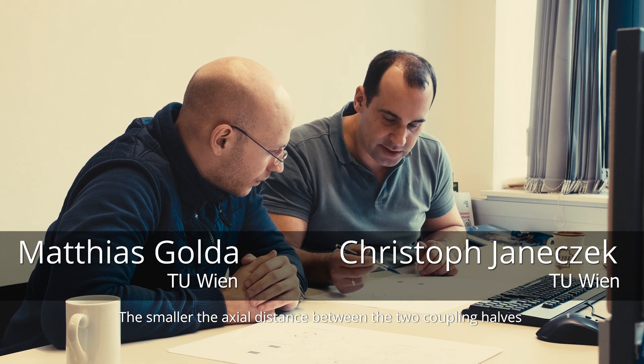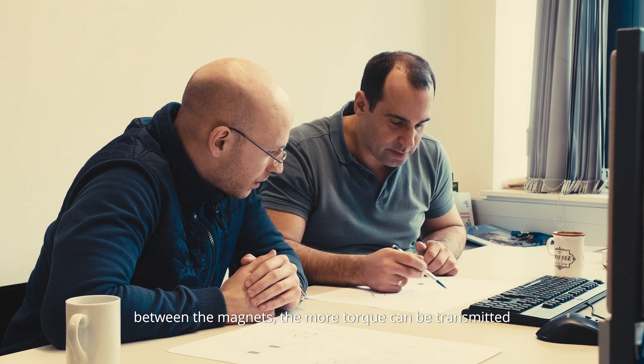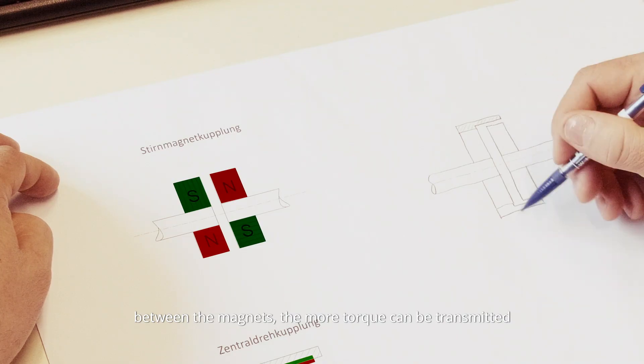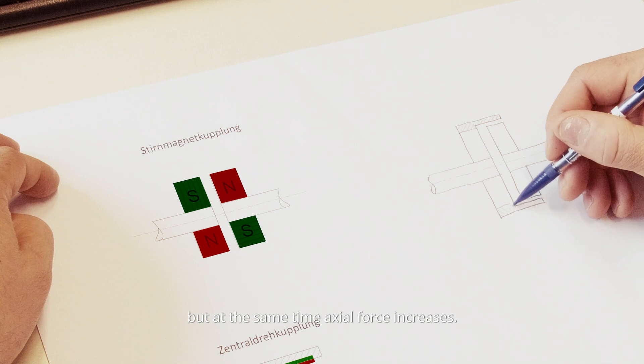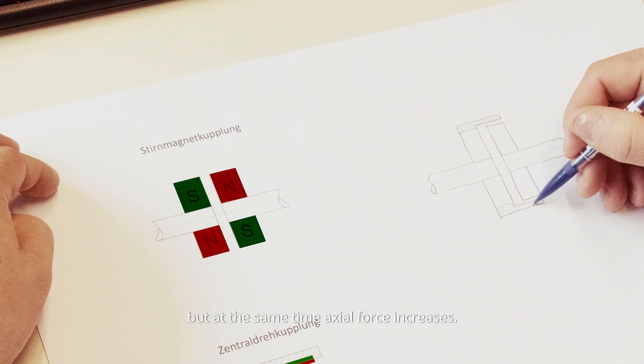The smaller the axial distance between the two coupling halves between the magnets, the more torque can be transmitted. But at the same time, axial force increases.